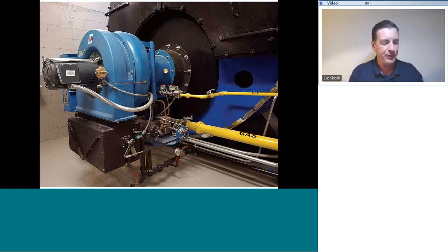Once the main burner has been lit by the pilot at a very small level, remember this combustion fan is blowing the whole time. Now this modulating motor will start to stroke to the fully open position, and it will open the combustion air damper and the butterfly valve in the gas line at the same time, allowing that burner to ramp up to full fire.